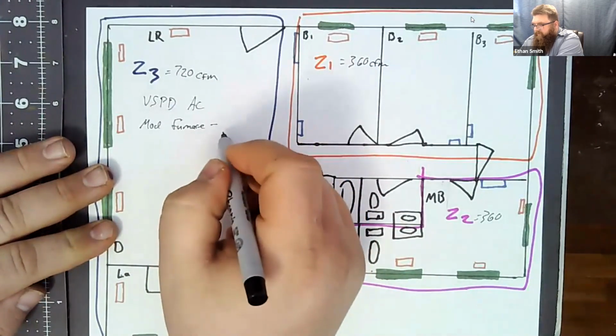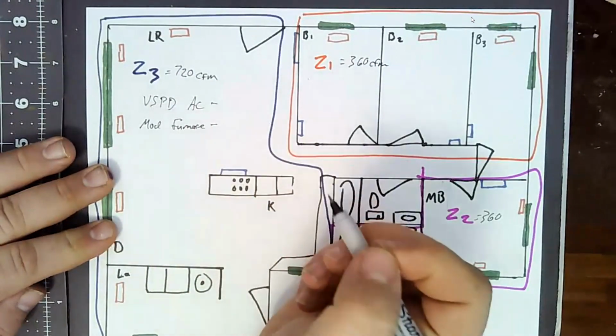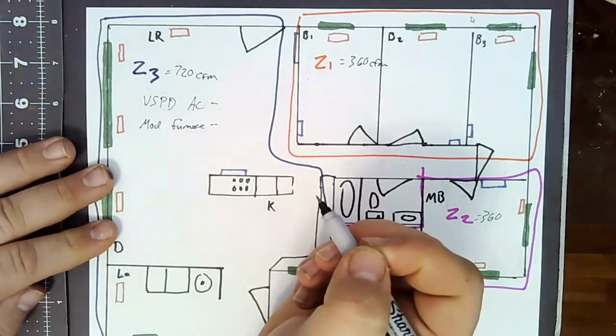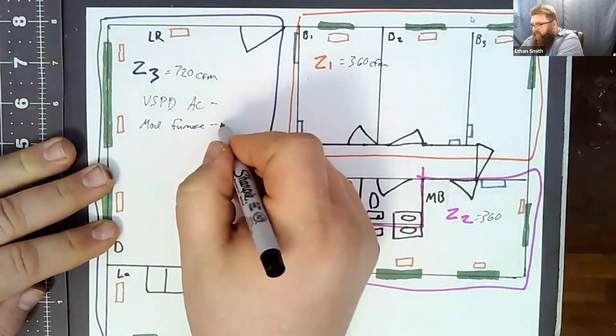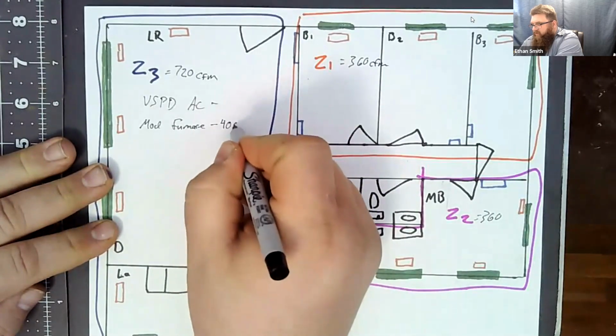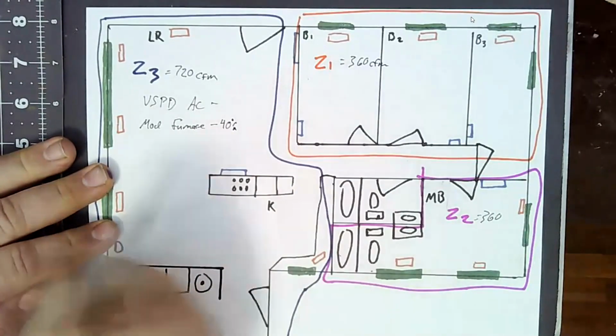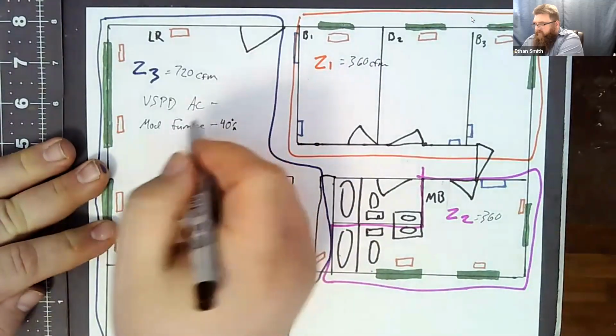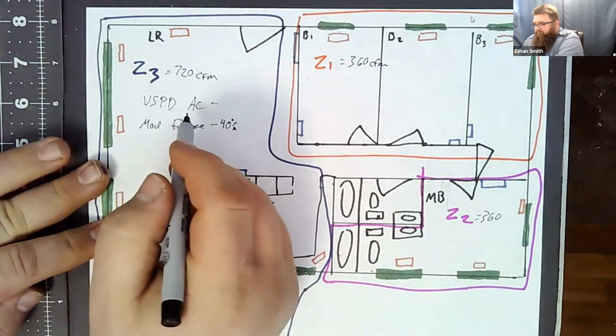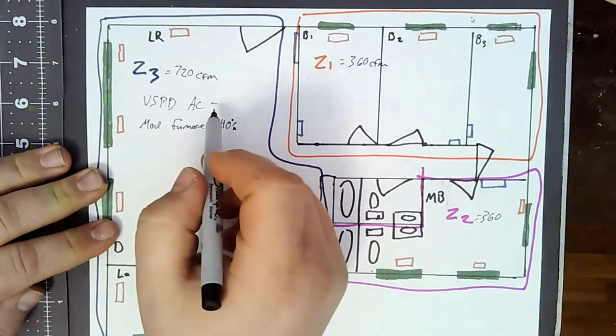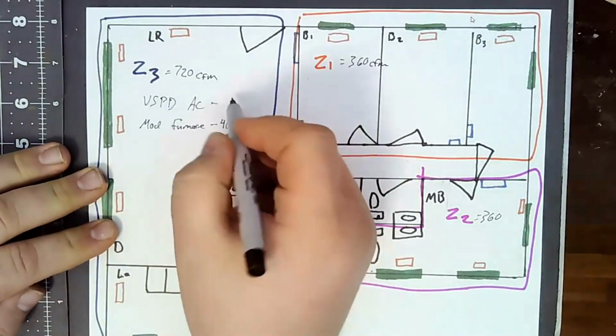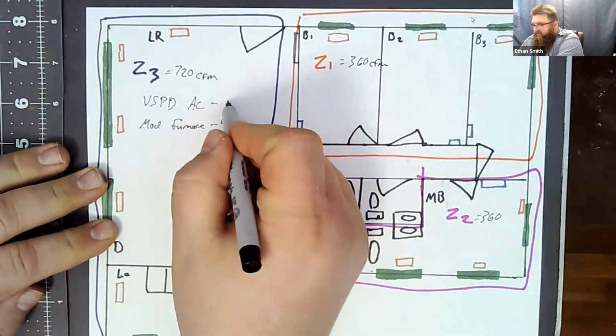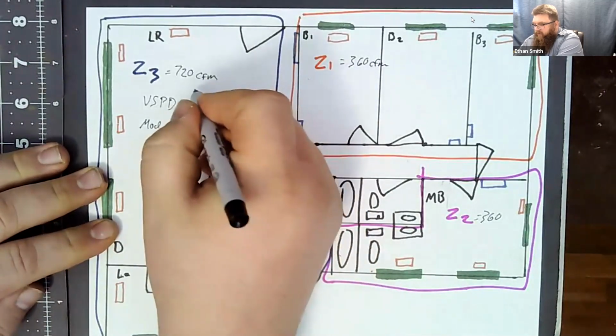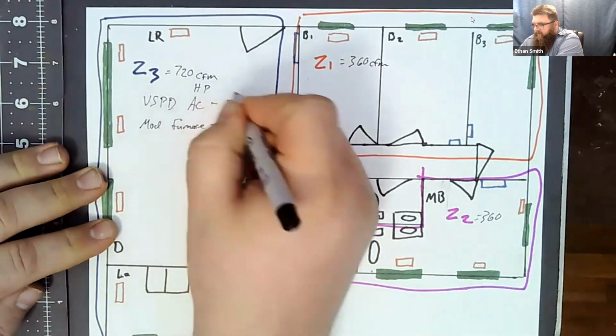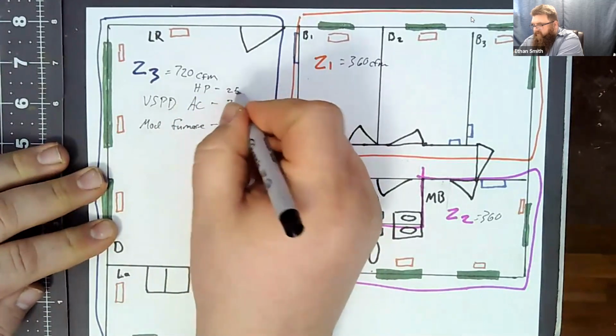I'm pretty sure the new ones do 50%. Now we actually do a little better than that. We can get down to 40. 40, okay. Minimum fire is 40% of total capacity. Used to be 30. No. The ACs will do 30. So the variable speed AC will do 30. Or if we wanted to do a heat pump, it'll do 25.